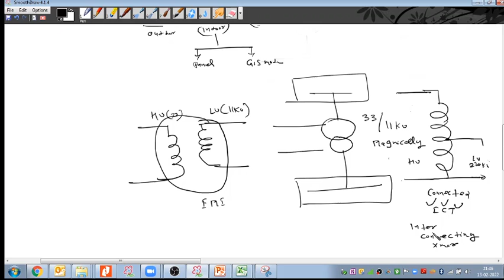So in place of the two winding transformer or three winding transformer, in this tender the client has written it as the ICT. So whenever you see the word ICT, you need to understand that this is the auto transformer. Here we will use the auto transformer because the voltage ratio is less than 2. And this is the power rating of the transformer.